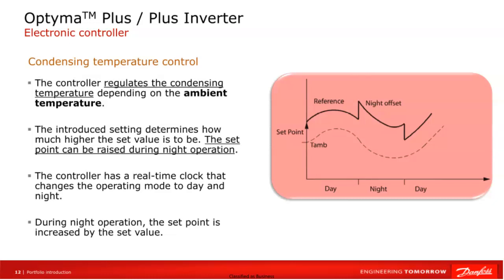Another interesting function is the ability to increase the condensing temperature during night operation. This allows us to ensure that the condenser fan runs at a lower speed at night, reducing noise levels. The controller has a real-time clock that automatically changes the operating mode to night and day. At night, the condensing temperature set point is increased by a certain amount, which allows the unit to operate more quietly. These controller functions are crucial for the efficiency and comfort of the unit operation.